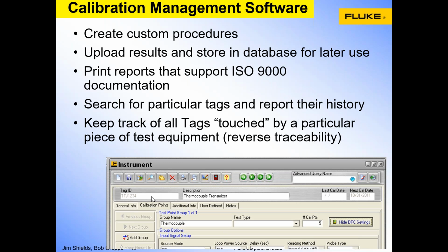You can go into the software, and if multiple calibrations have been performed on a particular tag over time, you can view and report their history, do trending. And one other feature that calibration management software can bring to the party is this: in the event that a calibrator is returned, let's say you return a 754 to Transcat for calibration, and the as found calibration failed, the milliamp measurement for some reason was out of specification. It doesn't happen very often, but it could happen.